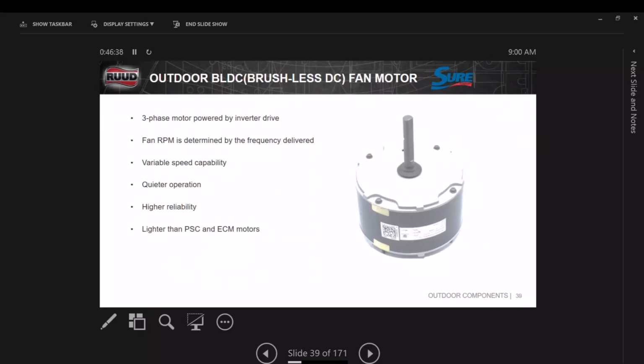Let's move on to the outdoor motor, the BLDC. The outdoor motor is a brushless DC motor. You'll commonly hear us say BLDC, which means brushless DC motor. It's actually a three-phase motor. If you had to check it with your meter, ohm it out, equal on all three legs. Just like you do a compressor that's three-phase, or any three-phase motor. The fan RPM is determined by the frequency. So in other words, that inverter board sends a PWM signal, which is frequency, basically from like 40 hertz to 60 hertz. It changes that frequency, and it causes the unit to be variable speed. Quieter operation, higher reliability, and it's a lot lighter than regular motors too.